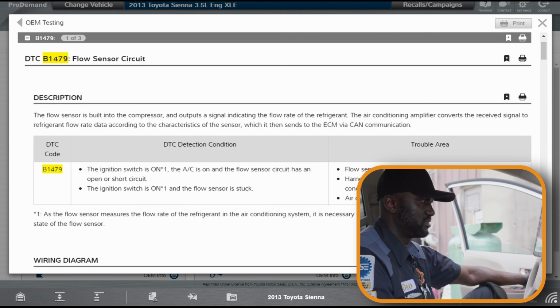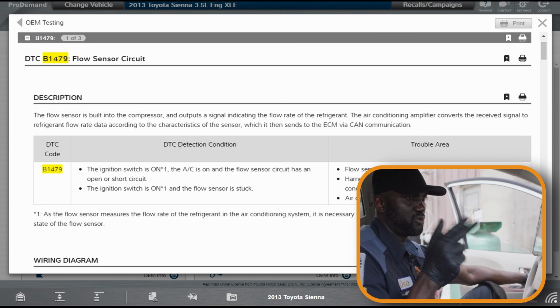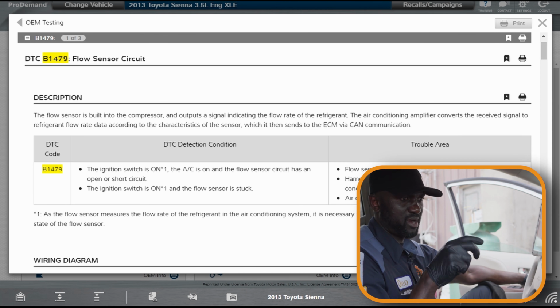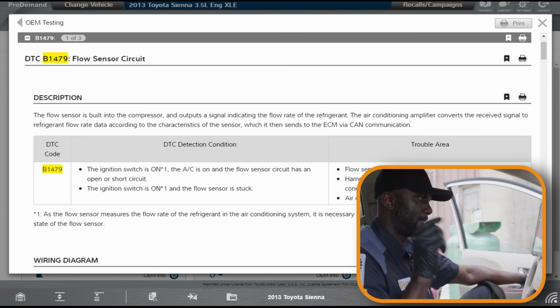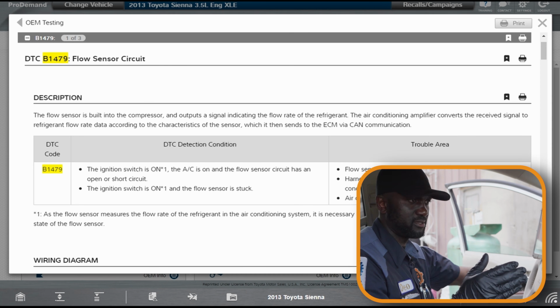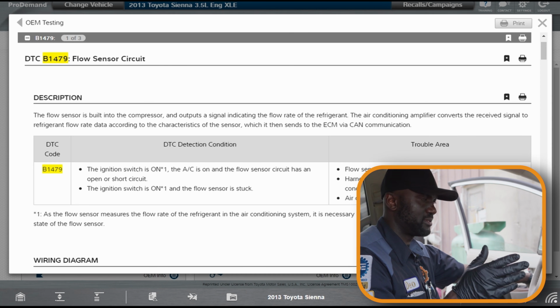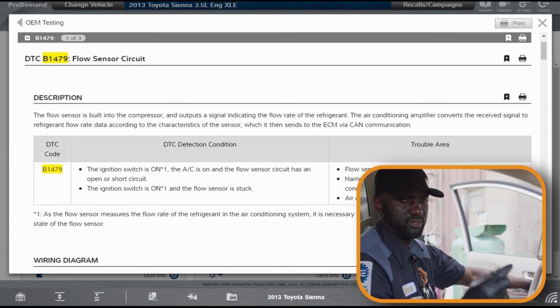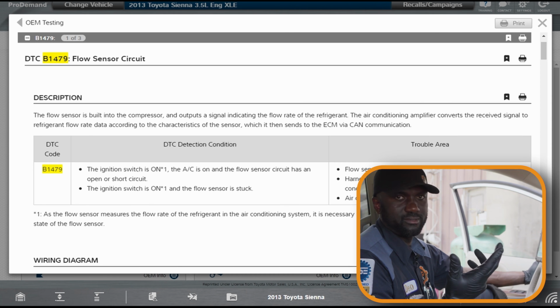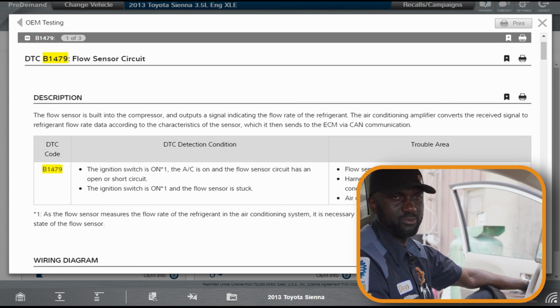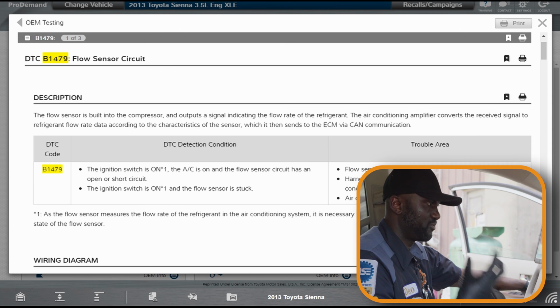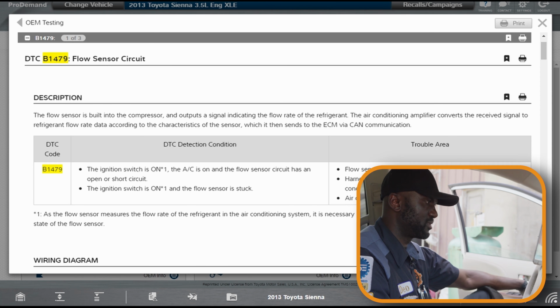At this point, testing this would be going to the compressor and back probing the wires of the sensor to see if we have control at the sensor. If we have control at the sensor, then the issue would be the sensor in the compressor. I believe we're probably not going to be able to get the sensor by itself, we'll have to replace the compressor.